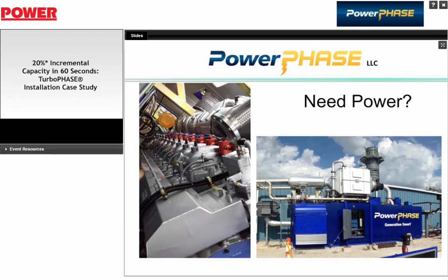And it was originally intended for steam injection. That's what they really meant when they talked about injection, because no one really had come up with a really cost-effective air injection product. But there really is no difference between steam injection and air injection, except the obvious that when you put more air in the gas turbine, it's just like it got a little cooler outside, and the gas turbine naturally picks up the extra power. So I'm pretty confident if the customers talk to the OEM, they're going to get a pretty favorable response, but I doubt we'll ever get an endorsement.